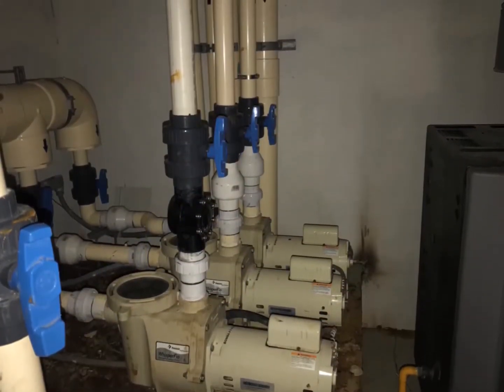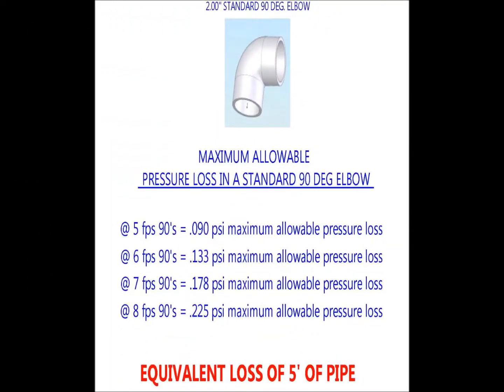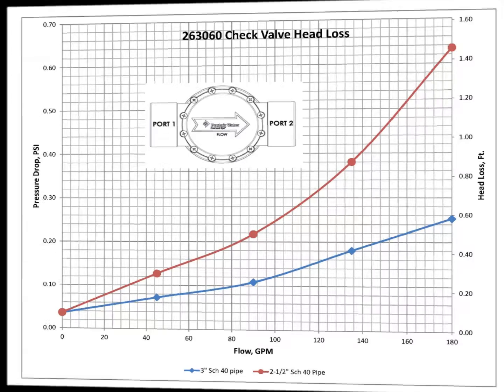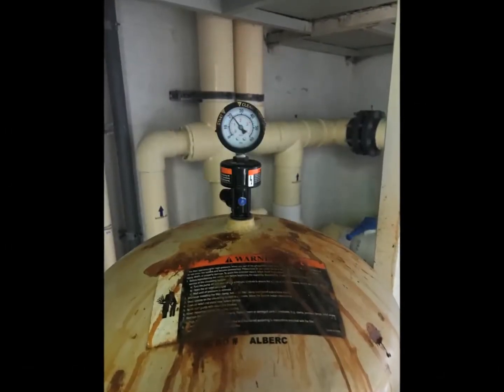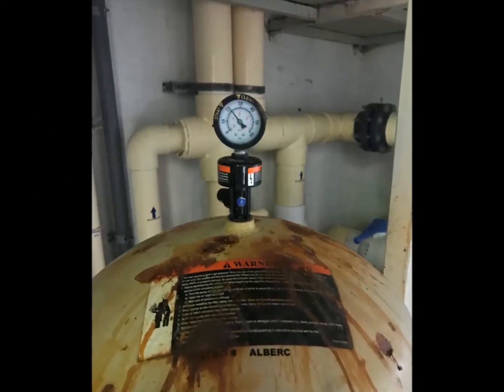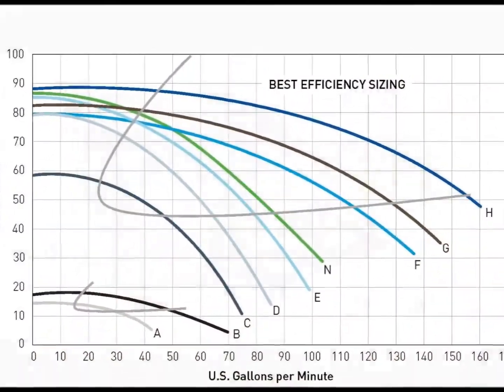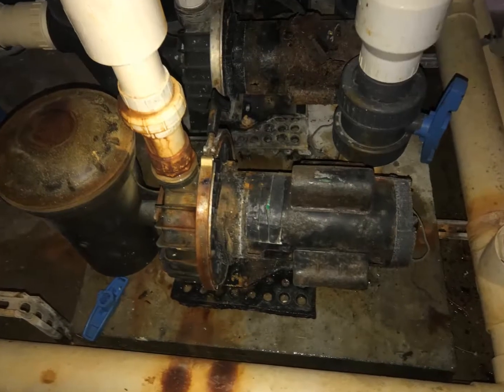This high velocity hydraulic head loss condition is exacerbated due to the length of horizontal and vertical pipe runs, 90-degree elbow changes in direction, isolation valves, check valves, and other factors in the equipment room that are inhibiting higher flows through smaller pipe sizes. A clean filter operating pressure of plus 20 PSI in combination with these influences results in a lower flow rate while using more energy. The excessive heat measured at the filter system pump motors also reflects a loss in energy efficiency and longevity to the pumping system.